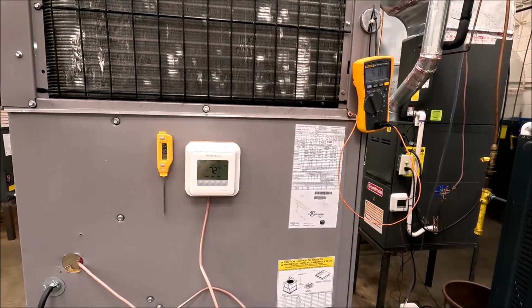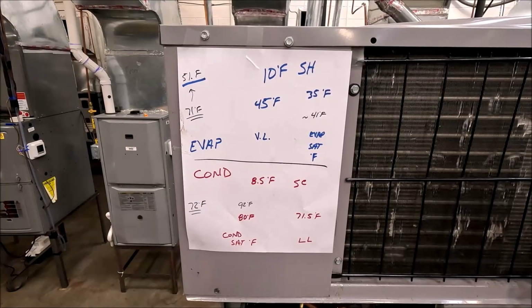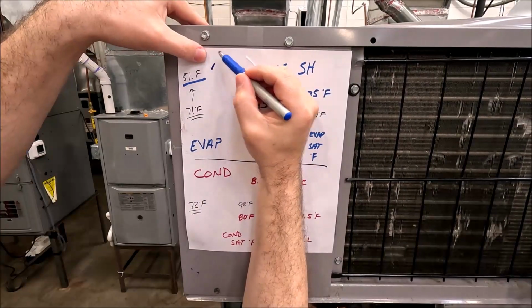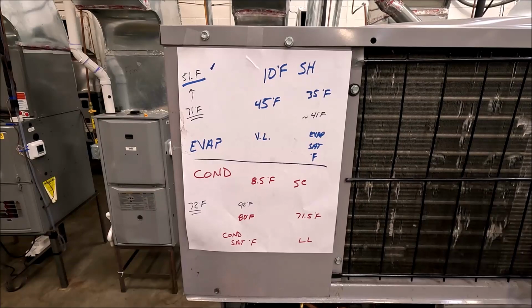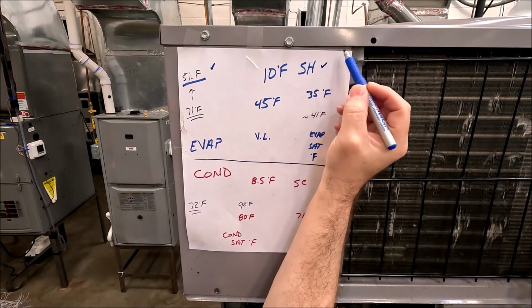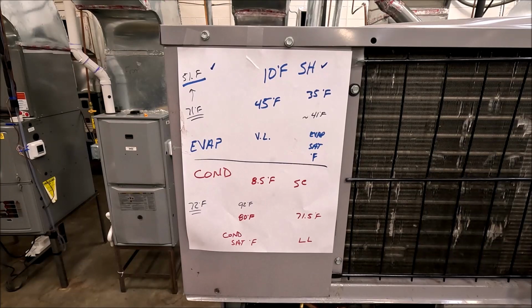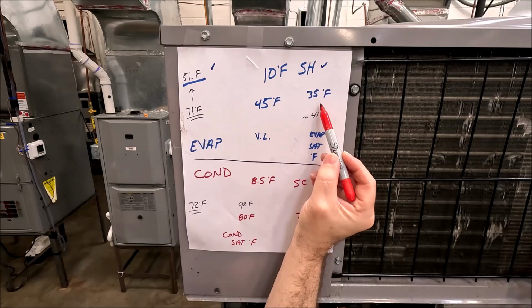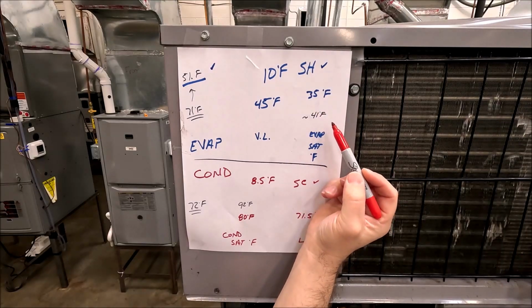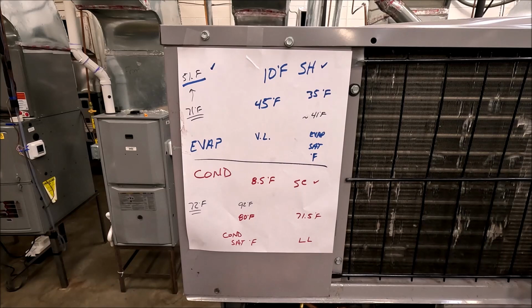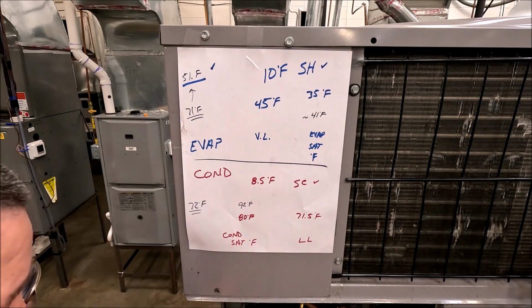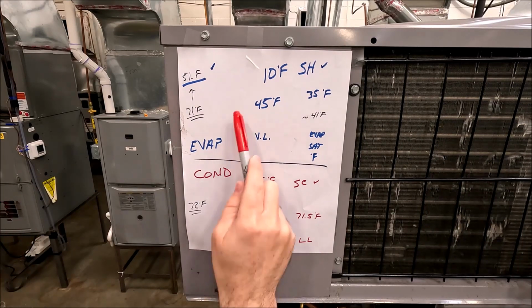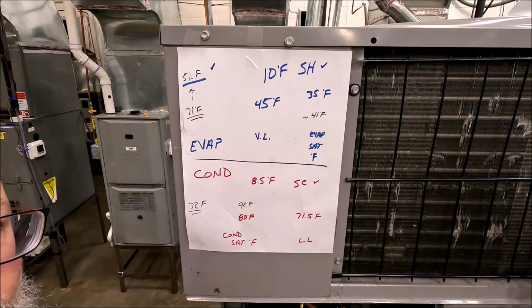Let's go look at the numbers. All right, so we estimated that 51 by taking a 20 degree drop off of the 71. That's good. Superheat, subcool, I mean, the superheat's good. The subcooling, I mean, it's okay. We were a little low on our saturation estimation. I can't tell you about that. I was a little low on my condenser saturation, so low on both of those. So that means the pressures are going to be low.